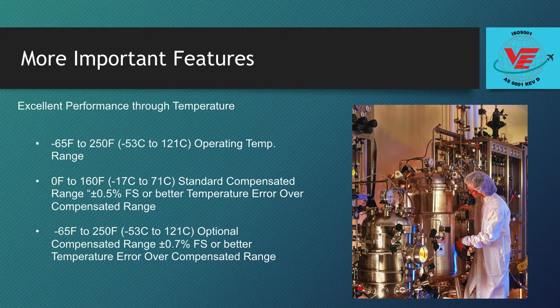The P365 can operate at temperatures from -65 degrees Fahrenheit to 250 degrees Fahrenheit. We offer two options for temperature compensation. The standard is 0 degrees Fahrenheit to 160 degrees Fahrenheit, and an optional wide range of -65 degrees Fahrenheit to 250 degrees Fahrenheit. The result is that the total error, including temperature effects and sensor error, is just 0.5% FS for the standard operating range.